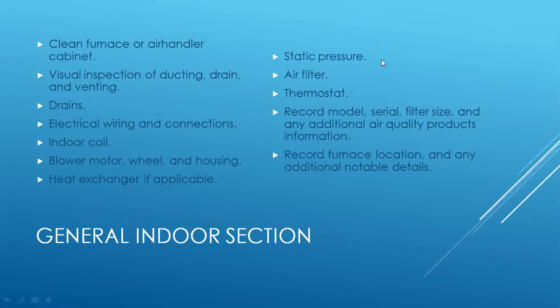you will burn the motors up. It can also actually do what they call a fold back. So if you run them so hard, they'll actually fold themselves back. So they'll slow themselves down to keep from overheating, which means you'll actually get less airflow. So it only takes a couple minutes to do a static pressure reading.